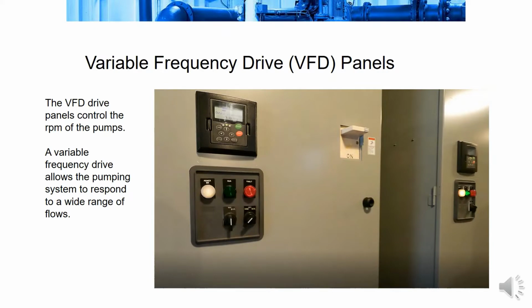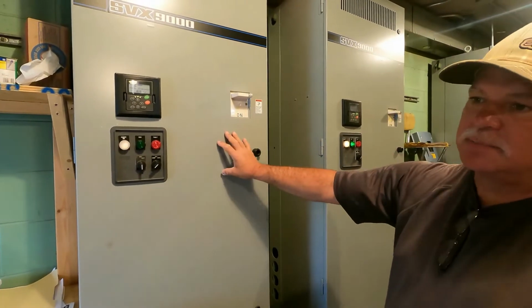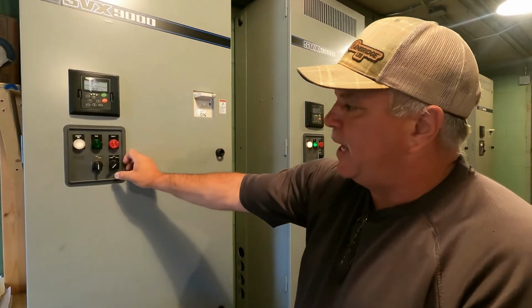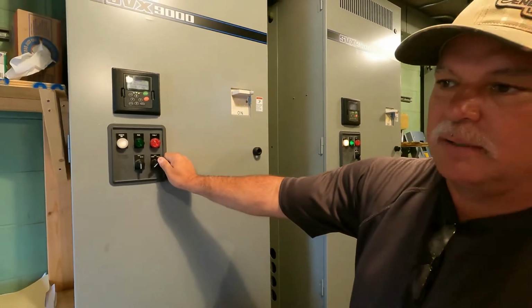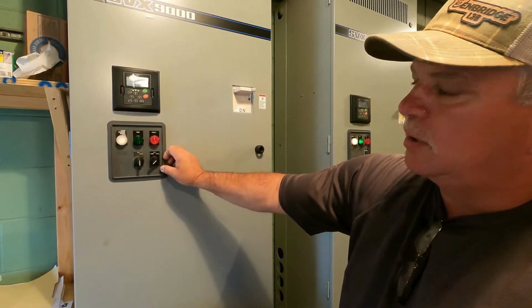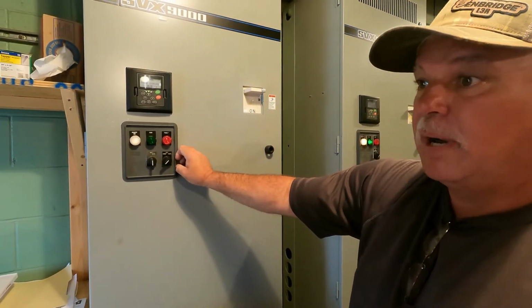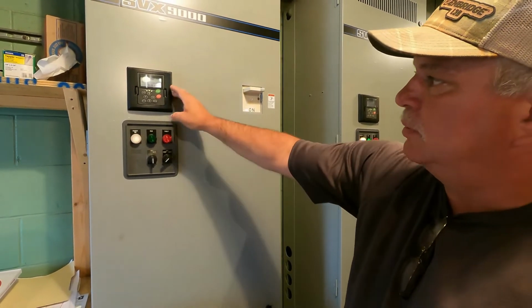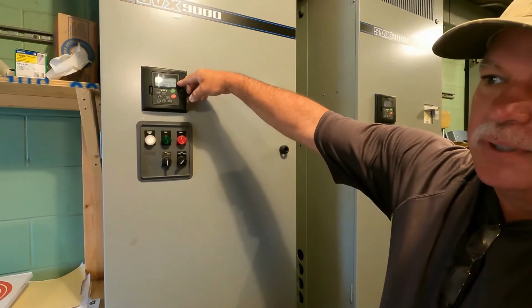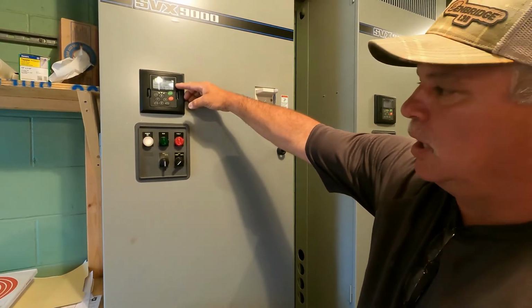Moving on to the variable frequency drive panels, these are used to control the RPMs of the pumps. The pumps should not be running at full 100% speed at all times and should be monitored and driven according to the level of water in the wet wells. So each panel is specific to each pump. It's got a hand-off auto switch, which basically means you can run it in manual mode, or you're currently running in auto mode by the PLC. So this would monitor frequency output as far as amps, voltage, and RPMs.